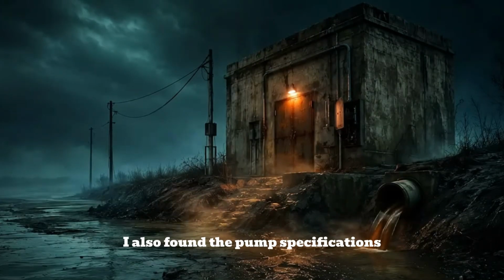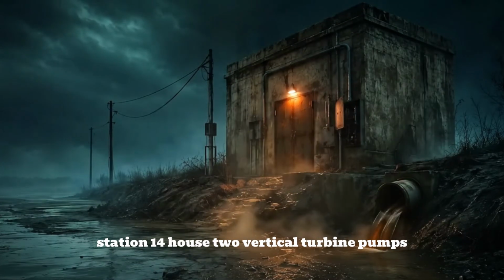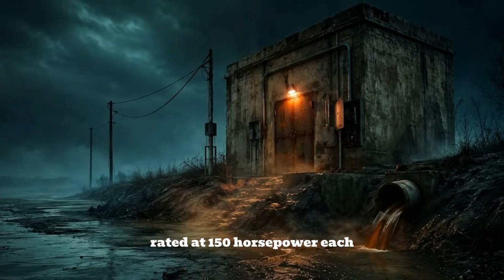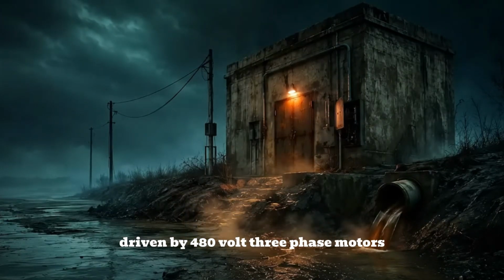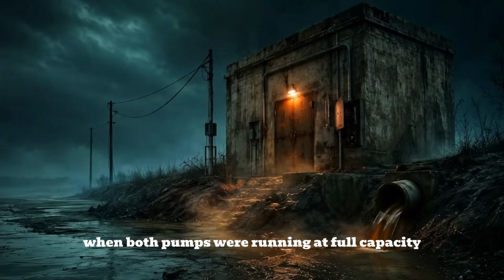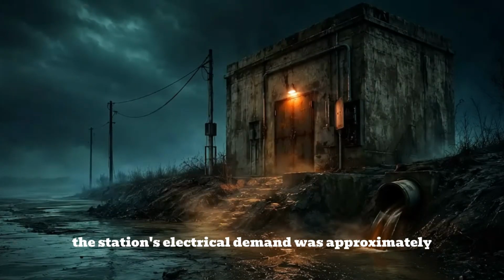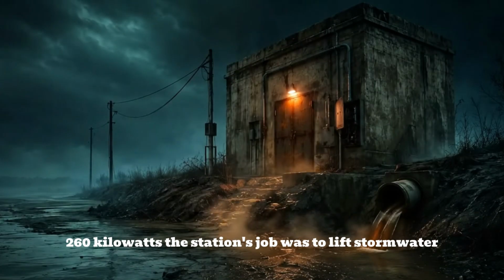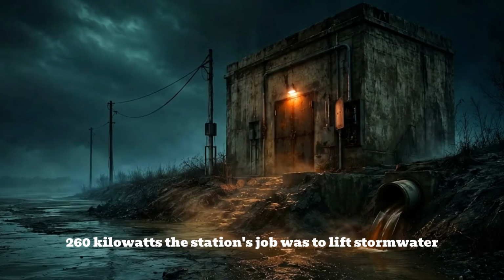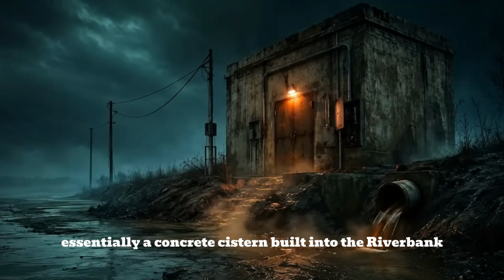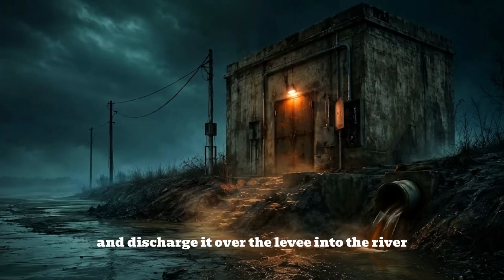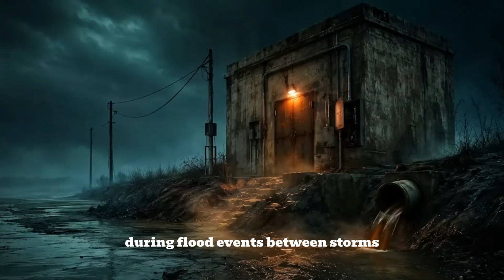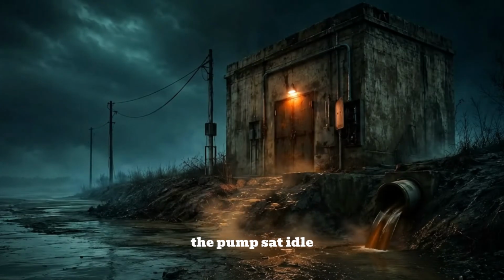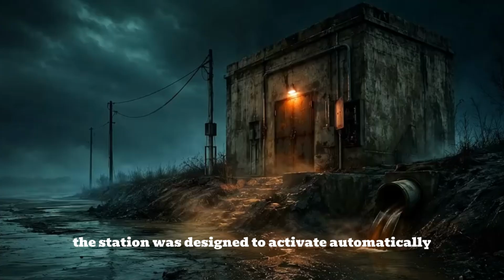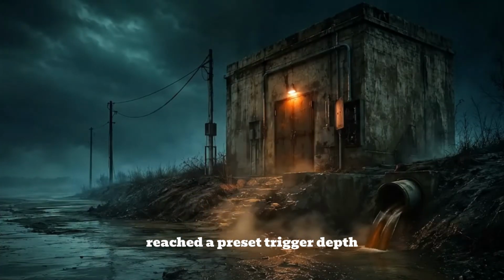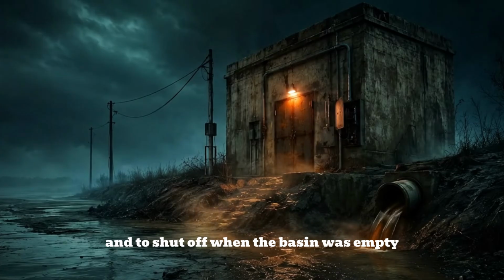I also found the pump specifications. Station 14 housed 2 vertical turbine pumps rated at 150 horsepower each, driven by 480-volt 3-phase motors. When both pumps were running at full capacity, the station's electrical demand was approximately 260 kilowatts. The station's job was to lift stormwater from a subsurface collection basin, essentially a concrete cistern built into the riverbank, and discharge it over the levee into the river during flood events. Between storms, the pumps sat idle. The station was designed to activate automatically when the water level in the collection basin reached a preset trigger depth and to shut off when the basin was empty.